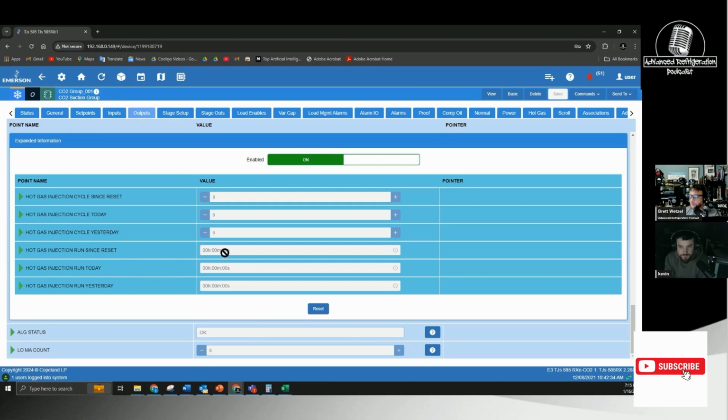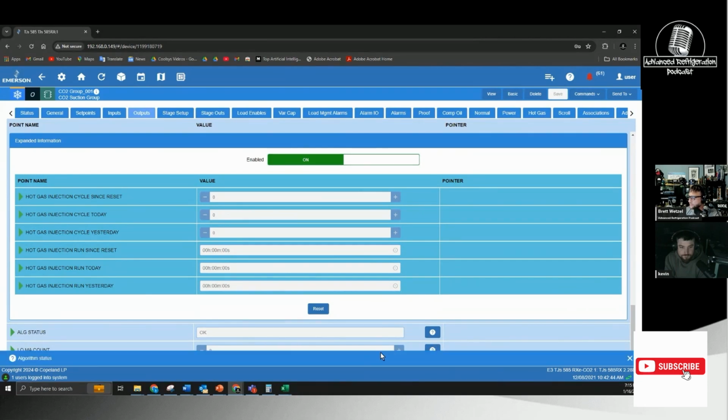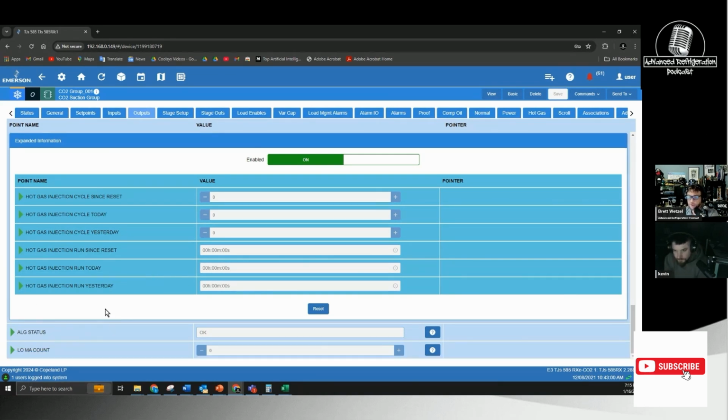No, but you could tie it to an alarm, right? Because I don't see anything here. Oh wait, LO MA count. What's that? I don't know what LO MA count. Oh, low multiple suction. Okay. What I was saying is, say it's been running 30 times a day for however long. If it starts running 50, you know you've got some kind of issue, like flood back coming back, before it actually becomes a super issue. It's on all day. Never.